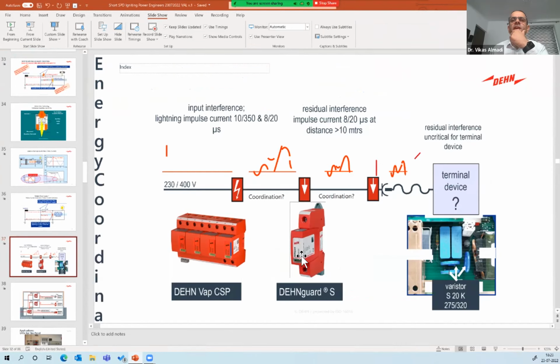With SPDs, you can remove the plug and retain the base there, but in case of an MCB you are removing the whole MCB, never just the plug. In case of a fault, suppose the MCB trips, we have to switch on the MCB. But in the SPD, when it is faulty it will become red. So we have to replace the SPD, right?